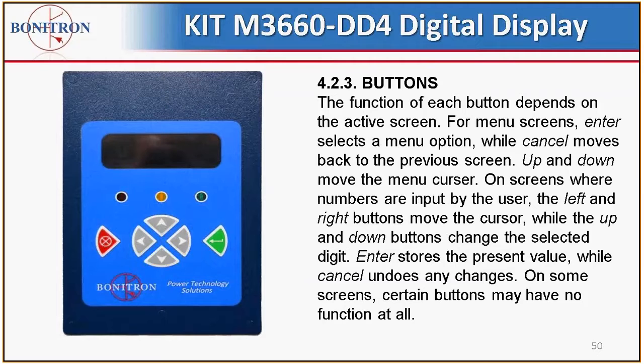The function of each of the buttons below the LEDs depends on the active screen. For the menu screens, enter selects a menu option while cancel moves back to the previous screen. Up and down move the menu cursor. On screens where numbers are input by the user, the left and right buttons move the cursor while the up and down buttons change the selected digit. Enter stores a preset value while cancel undoes any changes. Depending on the type of ride-through, of course, if you were just using SAG and there's no energy storage, the buttons that would indicate energy storage levels and things like that will have no function.